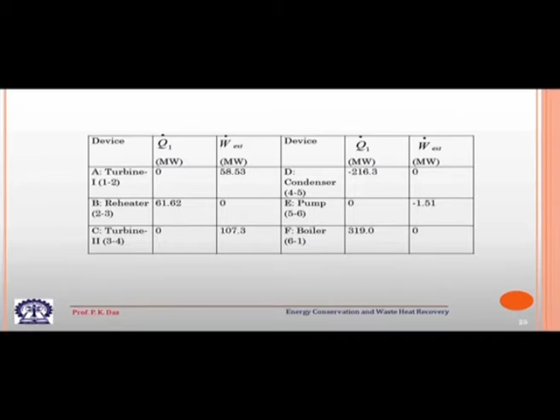Then we go to the boiler, and in the boiler there is heat transfer from 6 to 1. So, 319 megawatt amount of heat is added in the boiler. But for the total amount of heat addition, please pay your attention to this. First, the steam is heated and taken to the superheated condition for supplying it to the high pressure turbine, and again steam is heated in the reheater. So, total amount of heat addition will be 319 plus 61.62. This is the total amount of heat addition.